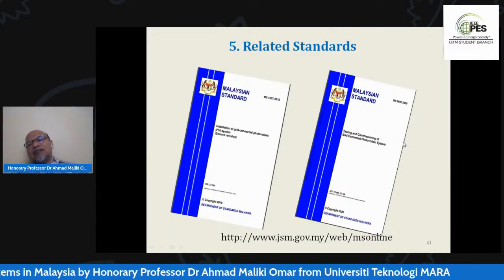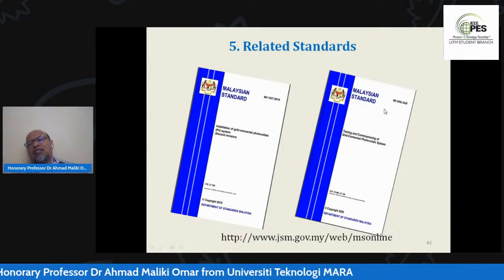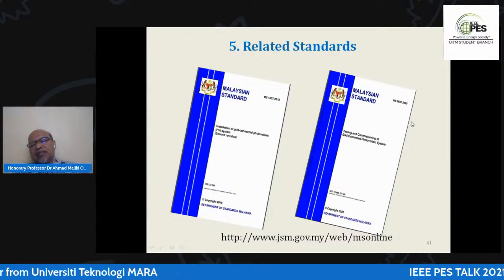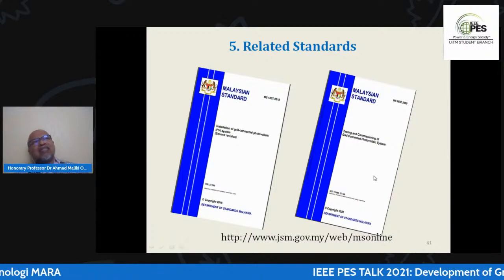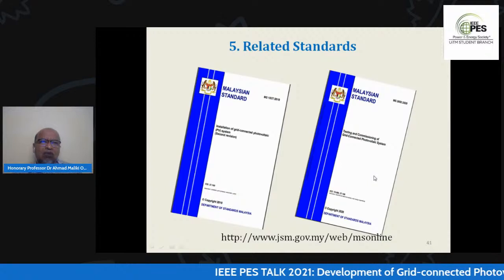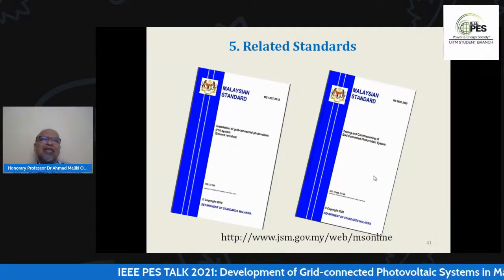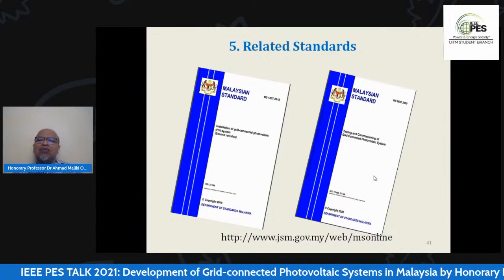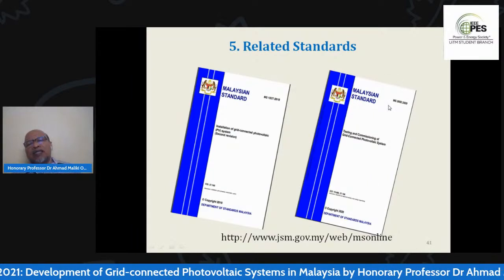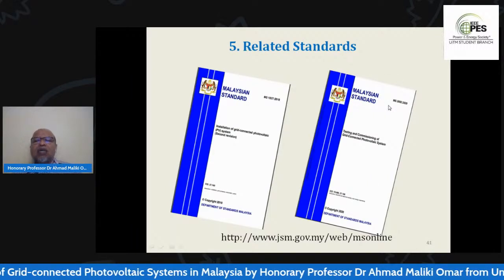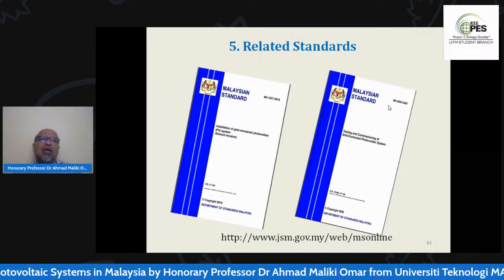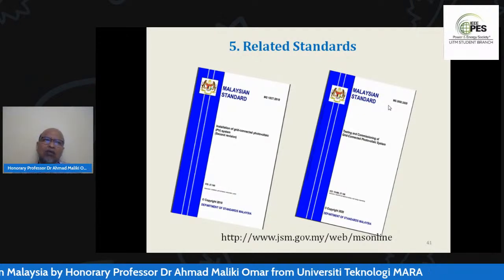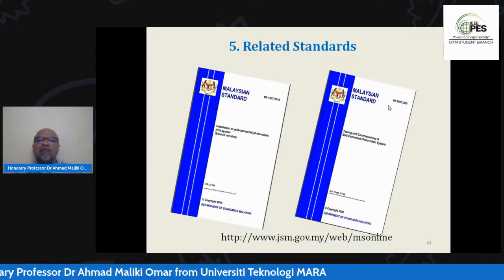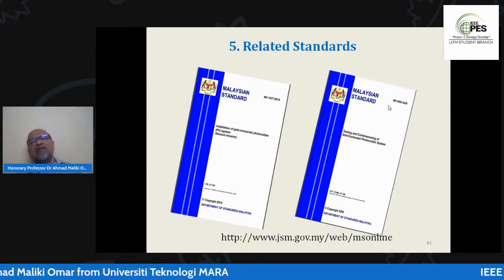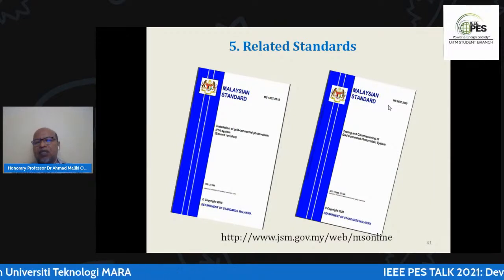Last year we managed to publish MS2692, in 2020. This standard is for testing and commissioning — after you install the grid-connected PV system, you need to test and commission it. It's quite detailed, with a checklist of things you need to comply with and tick off to ensure everything is in place and in order.